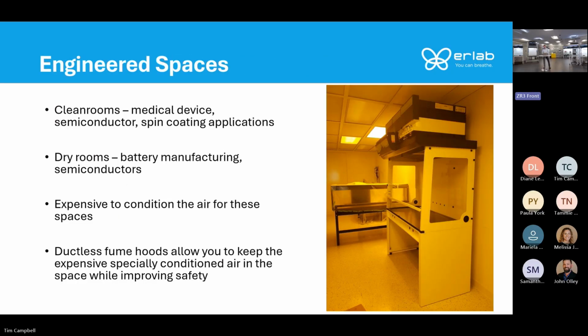Now on to engineered spaces. So in engineered spaces, I see a lot of open bench chemistry. When I talk about engineered spaces, they've been talking about clean rooms and dry rooms. So think about a clean room. A clean room, the goal is to have no particulates in there, very low level of particulates, maybe semiconductors, different types of applications where you can't have a high particle count. So you have about 20 to 30 air changes coming in through HEPA filtration into the clean room. It's typically going to be positive pressure because you don't want any particles getting in there.